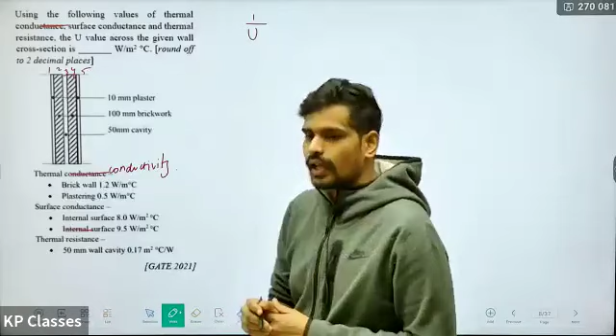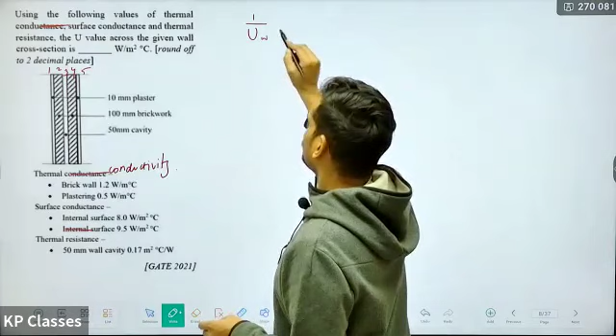So let us see how you calculate the U value of a multi-layered wall. There's no direct formula for U value. Rather, there's a formula for the resistance, 1 by U. 1 by U value of the wall will be 1 upon surface conductance of the outside surface plus, remember there are 5 layers here, so you will add the resistance of all 5 layers, R1 plus R2 plus R3 plus R4 plus R5, plus 1 upon surface conductance of the inside. That's the formula. But the resistance value is not directly given.